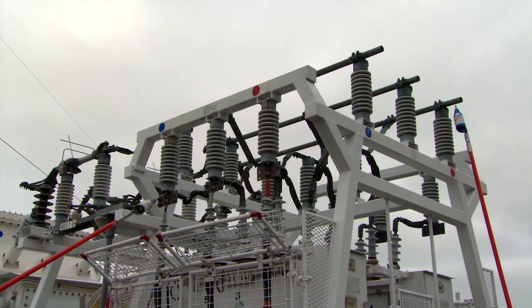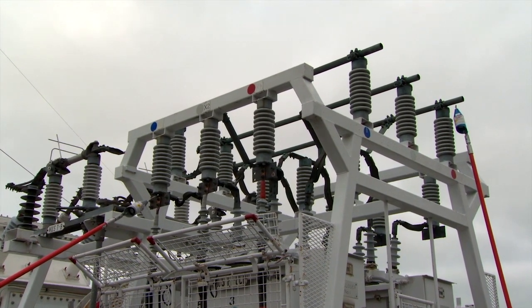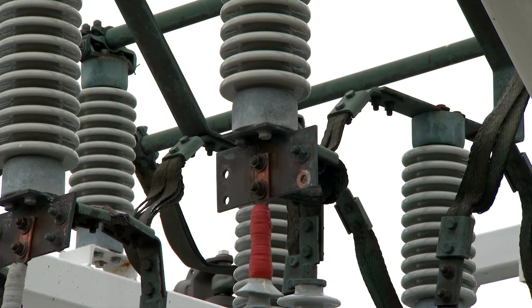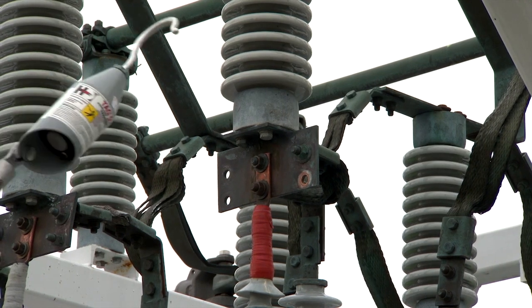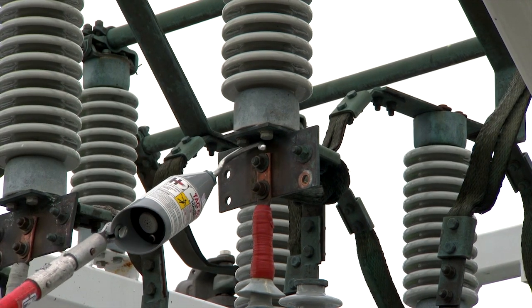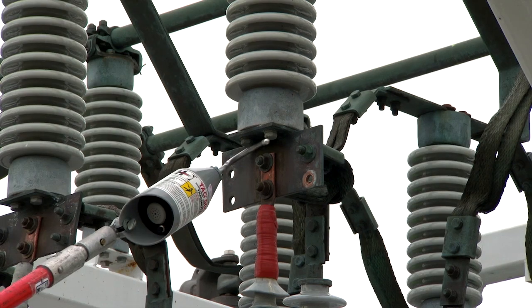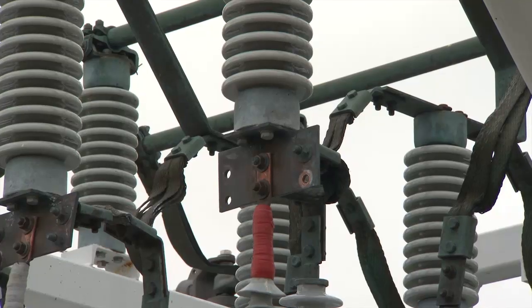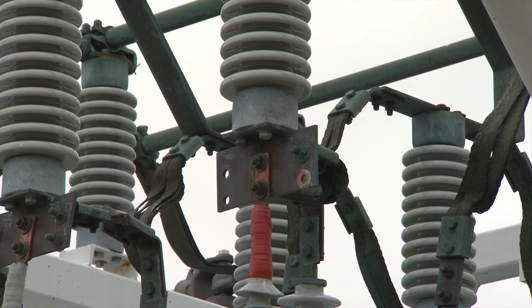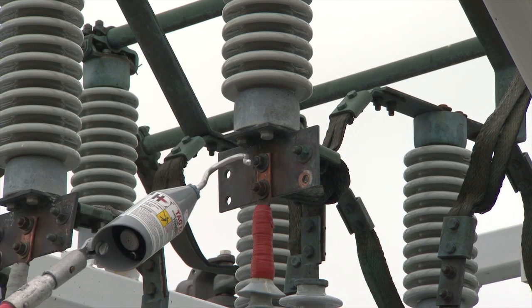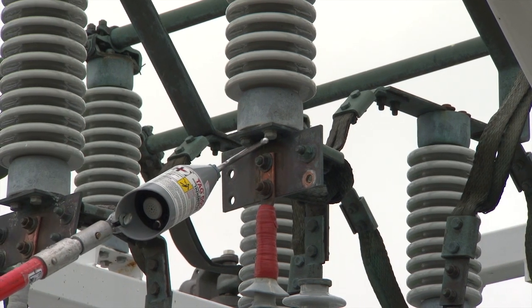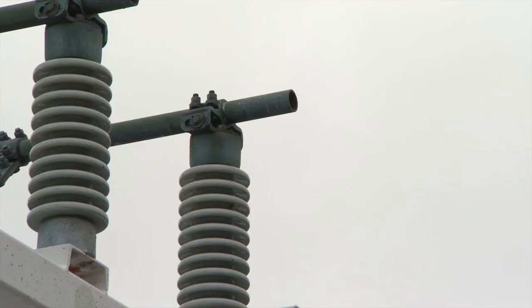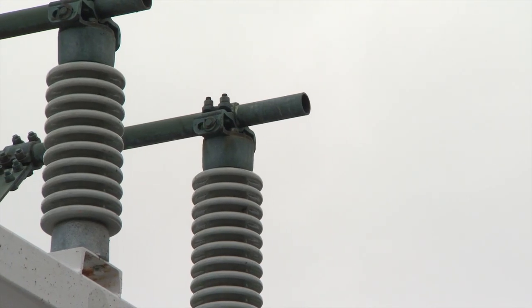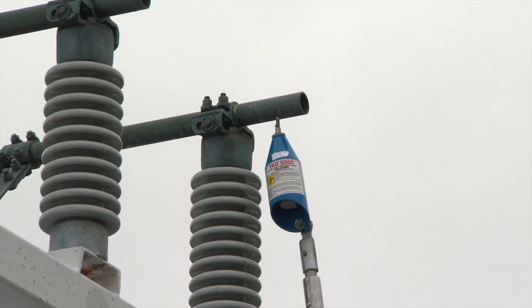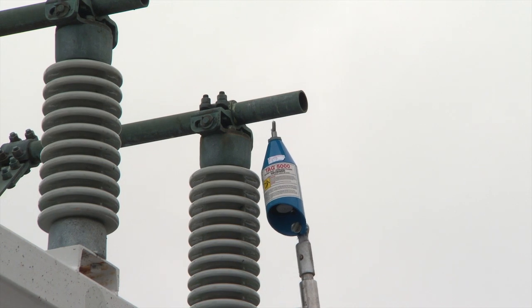If the conductors are in phase, the other 3 receiver lights will turn on, and the unit will emit a steady tone. If the conductors are out of phase, the receiver will supply a brief burst of all lights and a single short beep, but will not emit a steady tone. The TAG 5000 is not capable of indicating large in-phase voltage differences. Approved chance phasing sticks are the recommended testing equipment.